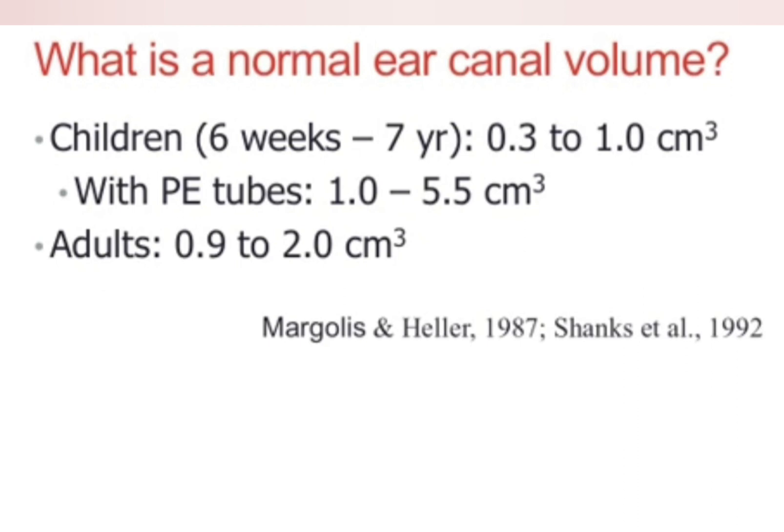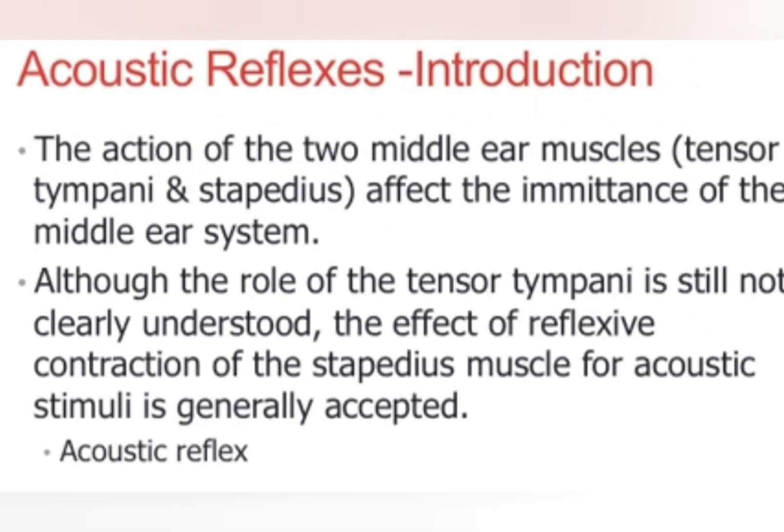Middle ear volume is important to know the ear canal volume — in adults it is 0.9 to 2 cm³. It can also help us predict whether a grommet is functioning or not, where it should be 1.0 to 5.5 cm³.